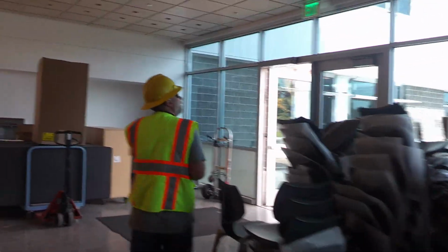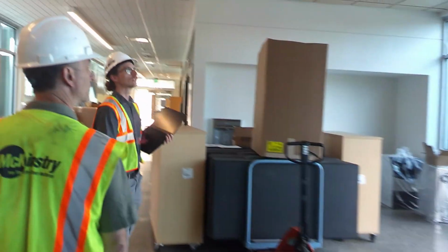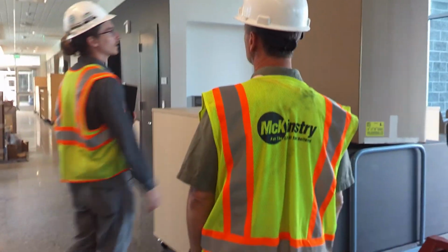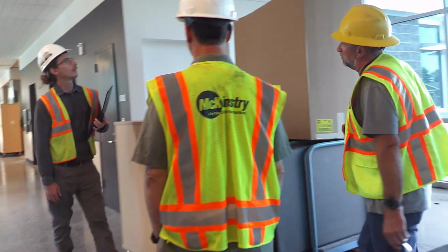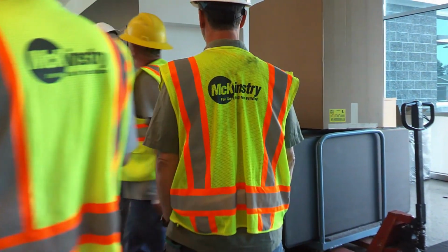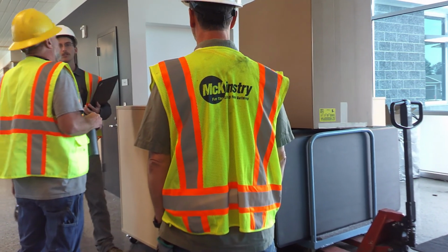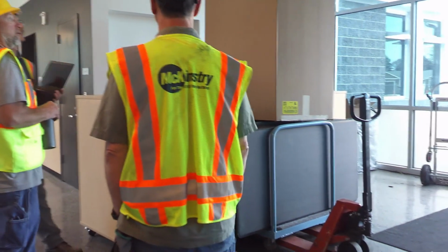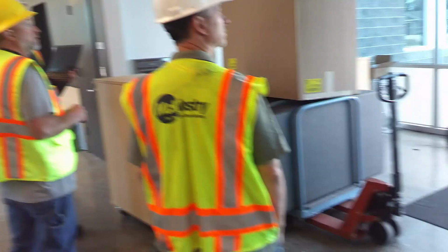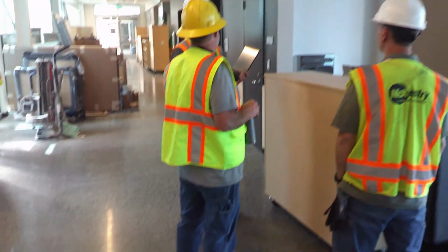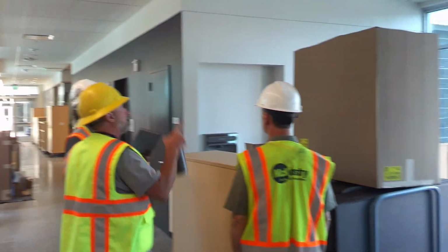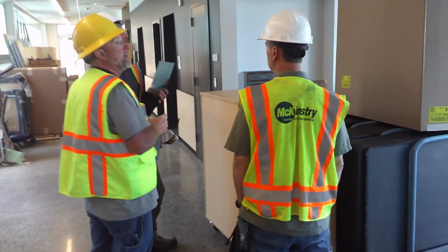Yeah, so these lights are all dimmed out right now because you've got that photocell picking up a pretty good amount of light. There's actually two there, huh? I'm trying to remember off the top of my head. I think it's just programmed on one of them because they're so close to each other, they're going to pick up the same amount of light. Sometimes there'll be oddities like that in the design, where instead of one in the middle, they put two for no reason.